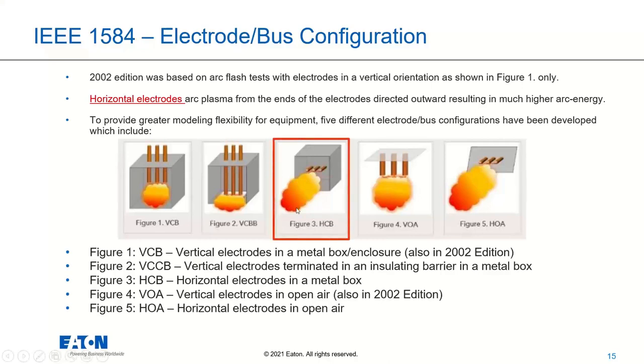But the most dangerous, and where we see the most incident energy, is really the center one, figure three, the horizontal electrodes in a box. You can see that the graphic here is showing the arc itself shooting out of the page, outwards towards the user. This is very similar to what we would see on a three-phase pad-mounted transformer, or perhaps a substation with terminal chambers on the sides, where those three-phase bushings are exiting horizontally out of the transformer, and you've got an enclosure where the only open side of that enclosure is really between the bushings and the user. That's going to make that arc propagate towards them, and that can be extremely dangerous.